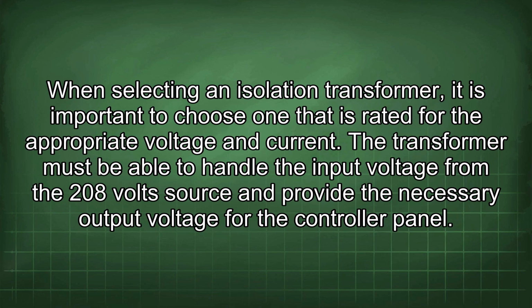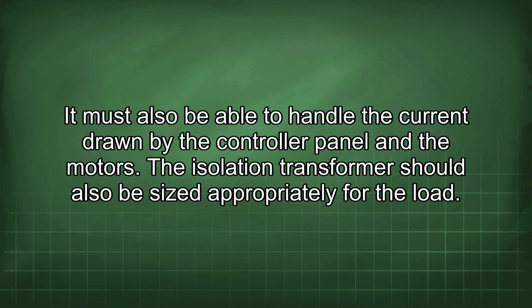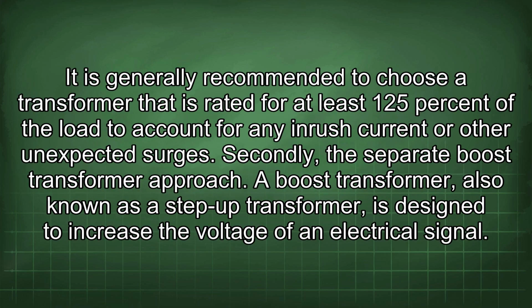When selecting an isolation transformer, it is important to choose one that is rated for the appropriate voltage and current. The transformer must be able to handle the input voltage from the 208 volt source and provide the necessary output voltage for the controller panel. It must also be able to handle the current drawn by the controller panel and the motors. The isolation transformer should also be sized appropriately for the load. It is generally recommended to choose a transformer that is rated for at least 125% of the load to account for any inrush current or other unexpected surges.